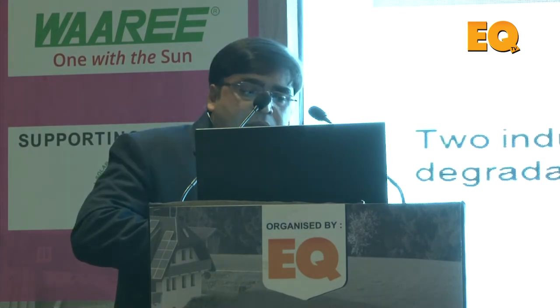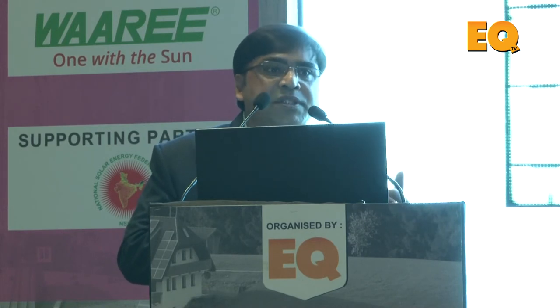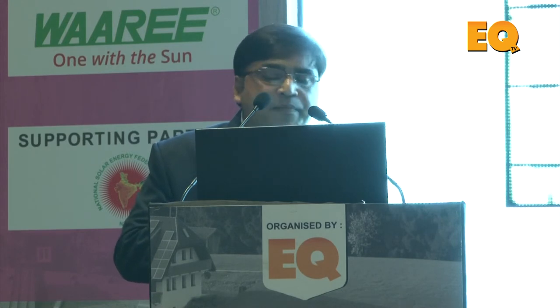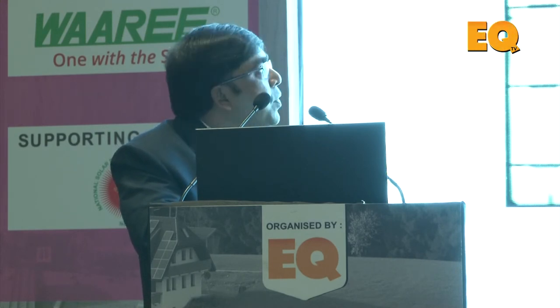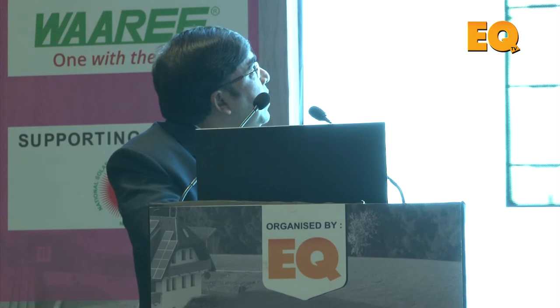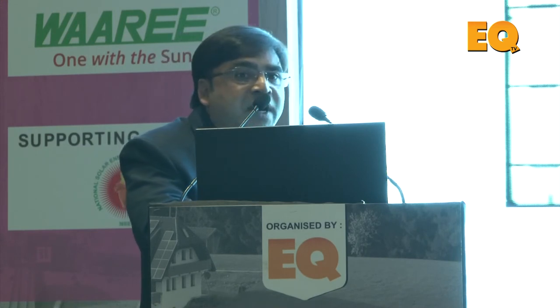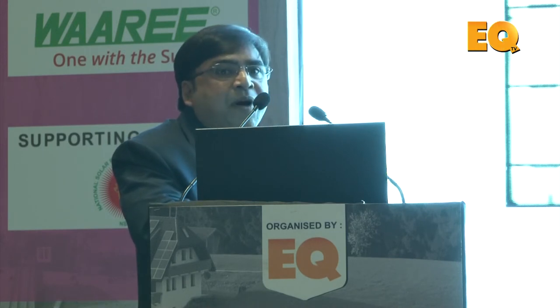Again, it's coming about the corrosion. What about that corrosion? The moment the acetic acid is coming, and the IEC is telling that you put it through 1,000 hours of damp heat, and if your module doesn't degrade below 5%, you are safe. We have tested this one kind of encapsulant, which is acetic acid free, the POE, and these are two different kinds of EVA, the good quality EVA. At 1,000 hours, they fall below 5%, they pass the IEC test. The moment it goes to 2,000 hours damp heat, you see what is the performance of them.